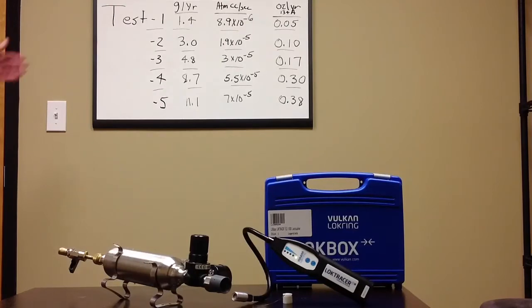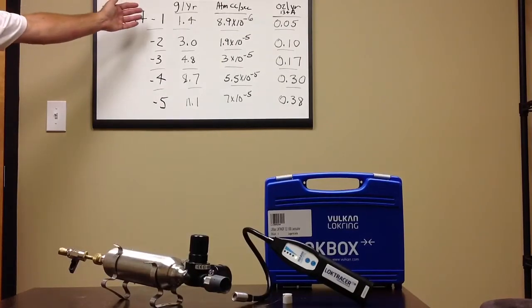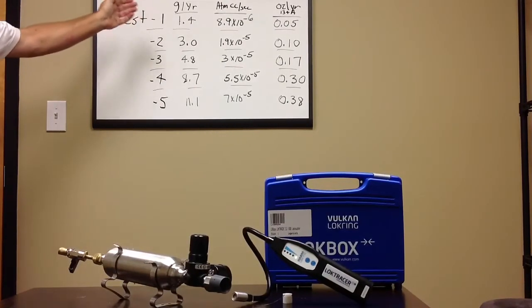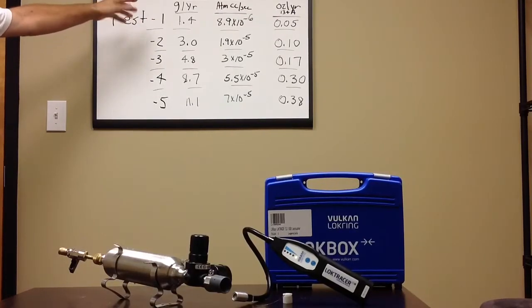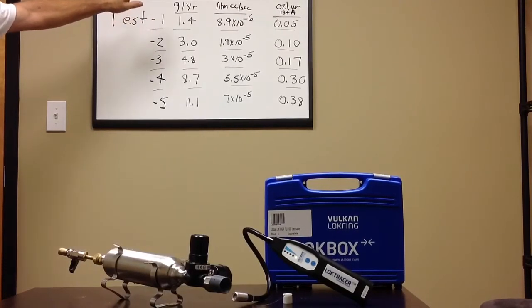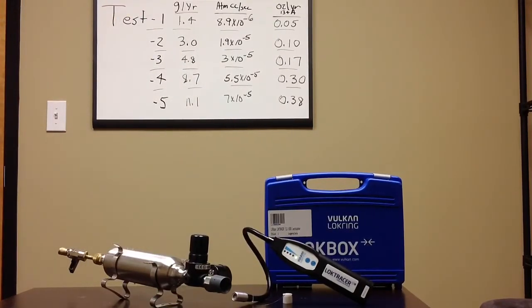These are going to be my test points that I'll adjust the leak to. I've got five different test points. I've got three different types of measurement units: grams per year, atmospheric cc's per second, which is a helium equivalency, and ounces per year of R134A.